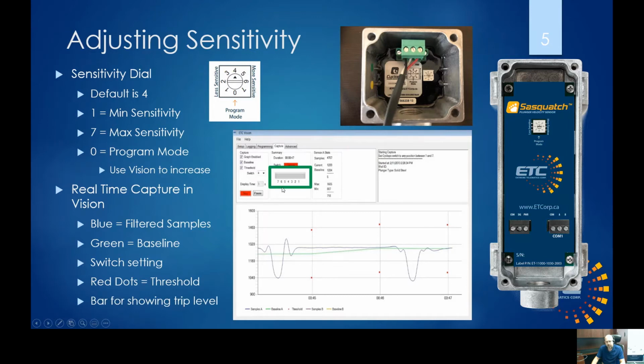Also, one other special feature built into Vision is if you're using this when you're commissioning, this will show you in real time as the signal changes what switch setting it would have triggered on. So even if you're on 2 or 3, it'll show you that you would have been able to trigger on setting 7, for example, when a plunger arrival comes in. So you can use that in real time to help decide which setting to put your sensitivity dial on.